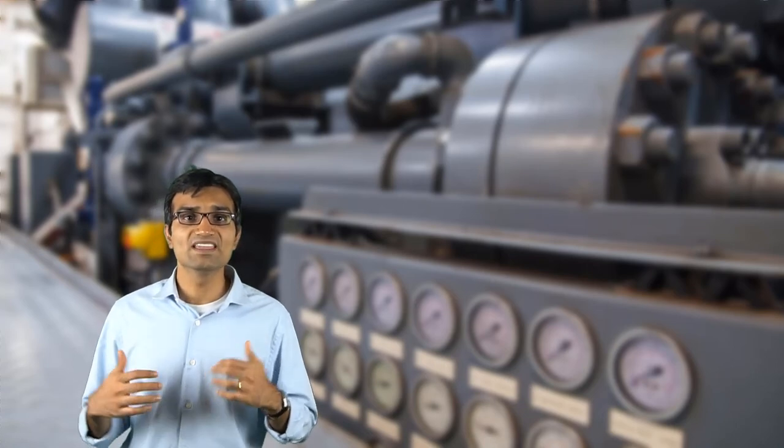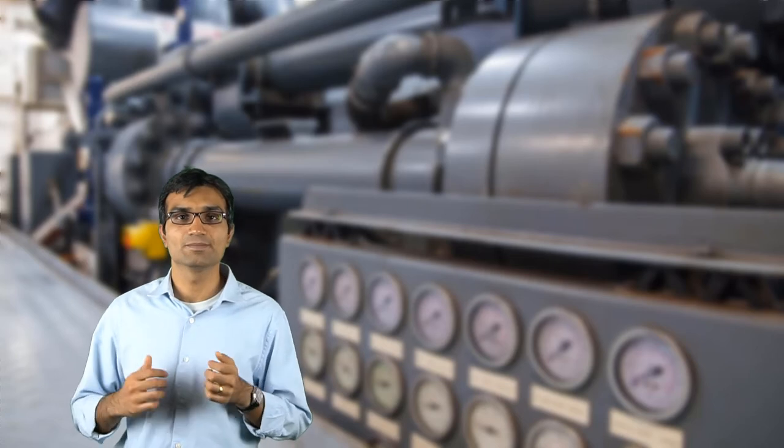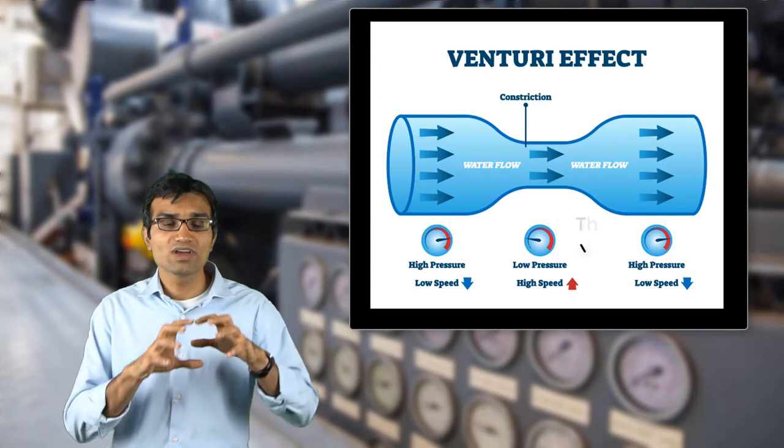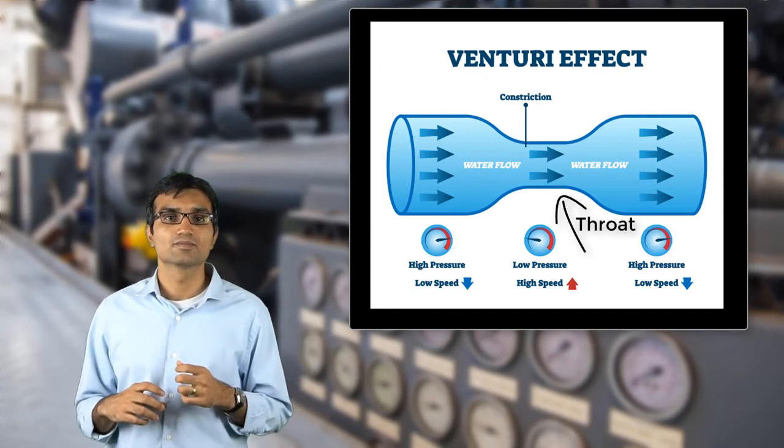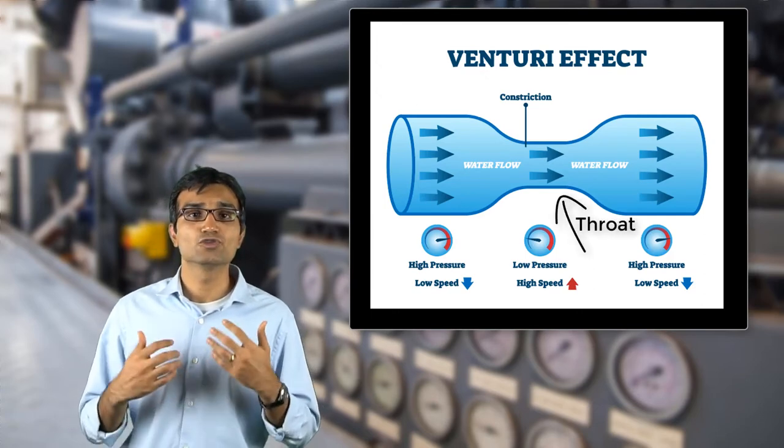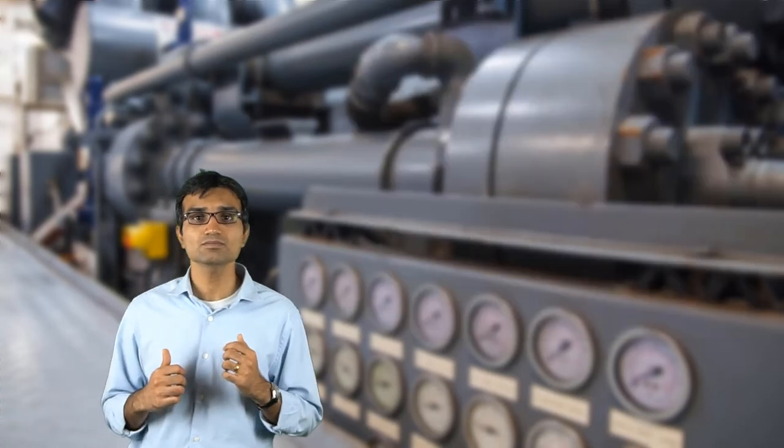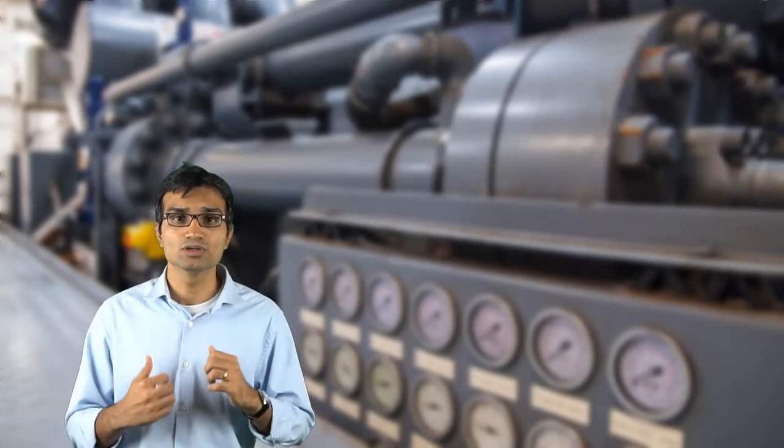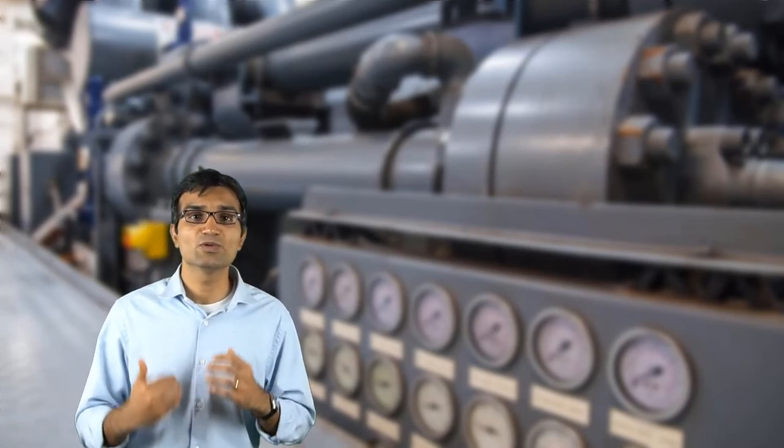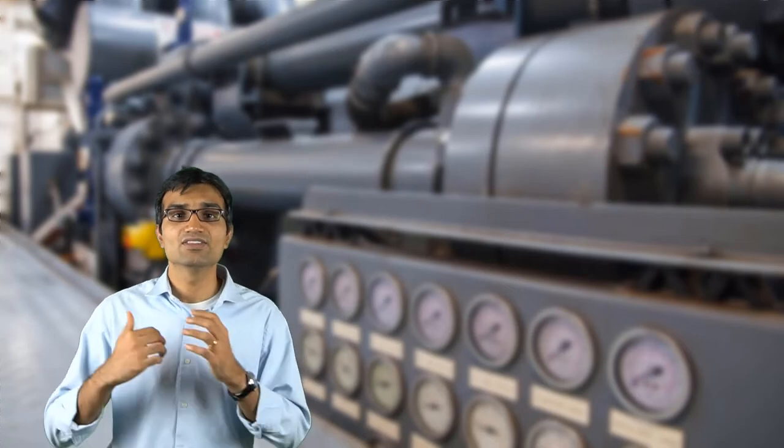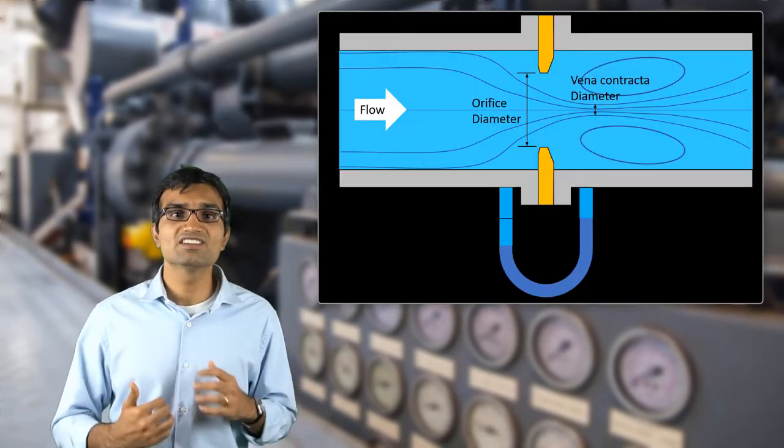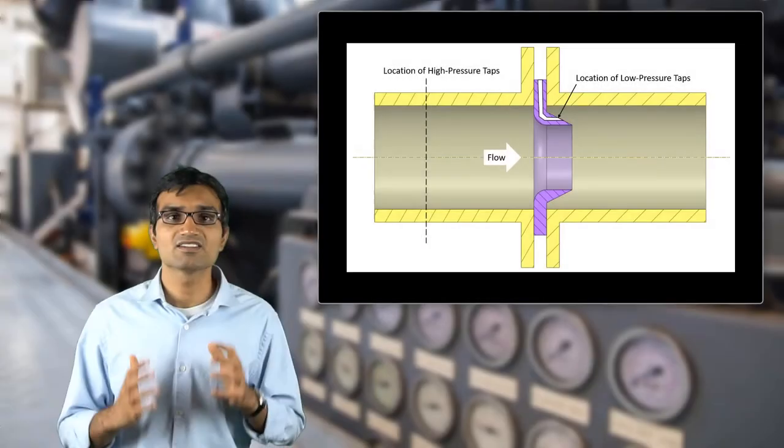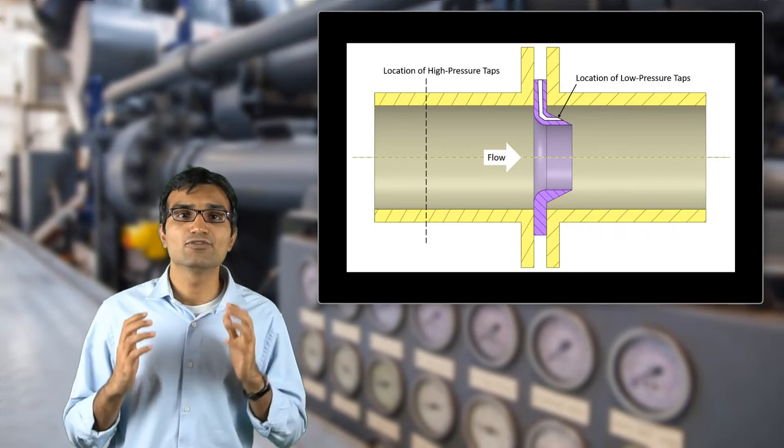A venturi tube is another common way of measuring fluid velocity. The venturi tube has a narrow section where the flow gets restricted. This section is commonly referred to as the throat of the venturi. Velocity is calculated based on pressure drop measurements across the throat and by taking the area ratios between the upstream section and the throat. A similar principle for measuring the mean velocity of the fluid is provided by devices such as orifice plates and flow nozzles.